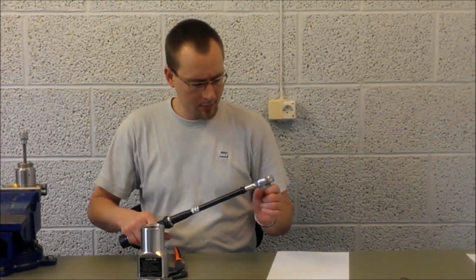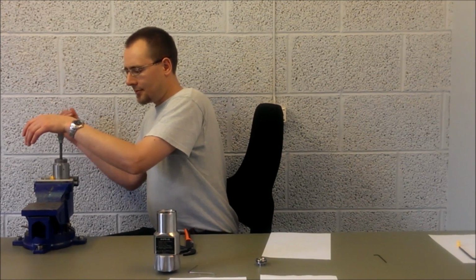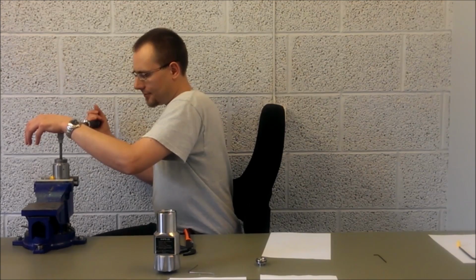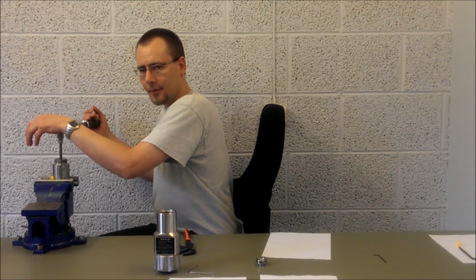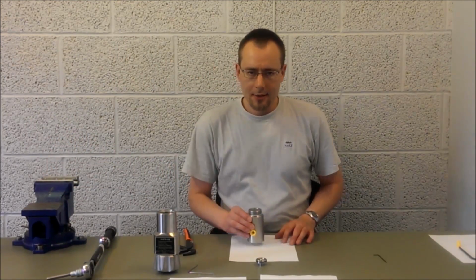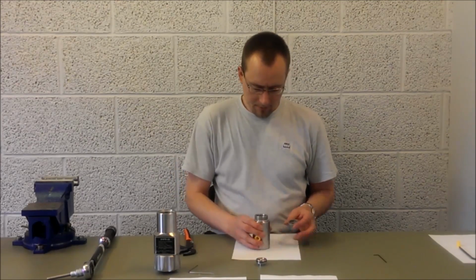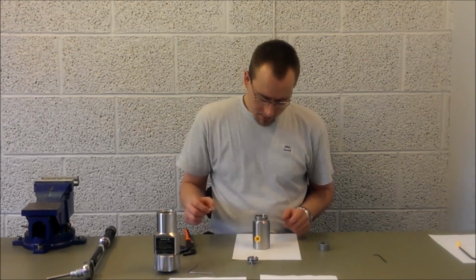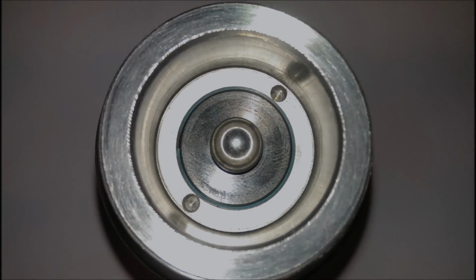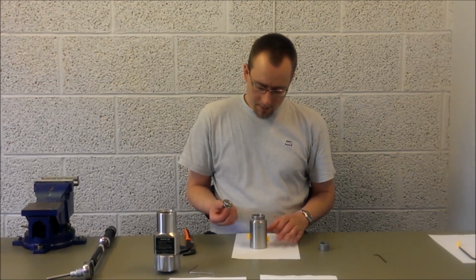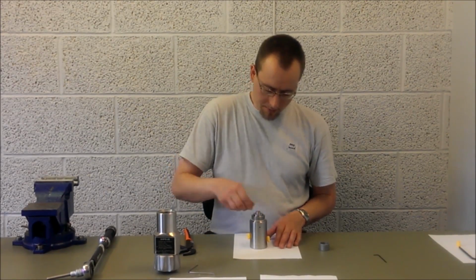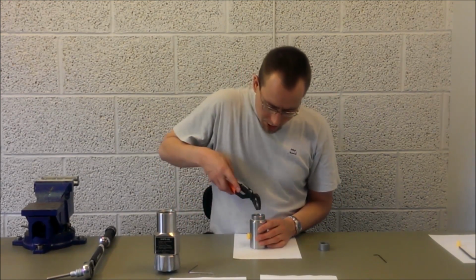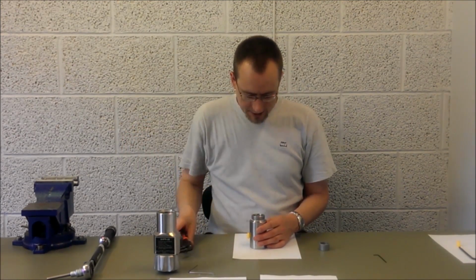The correct torque is 40 Newton meters. Maintain pressure of the tool towards the housing. Then apply the torque. 40 Newton meters is good. Take it out of the fixating device. Take the metal ball in the center. Then put the piston with the O-ring on top. Make sure that the metal ball is in center.